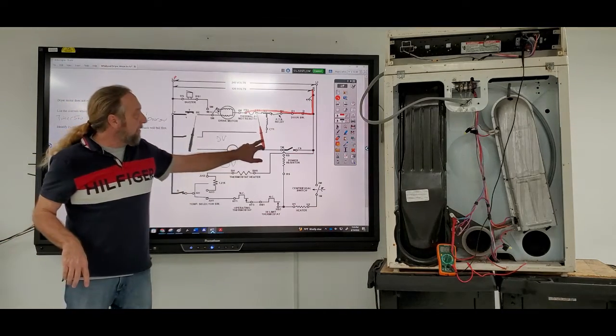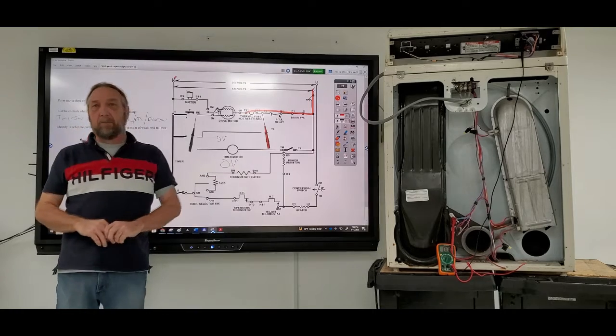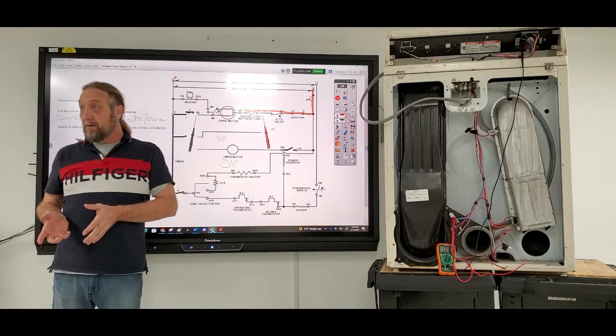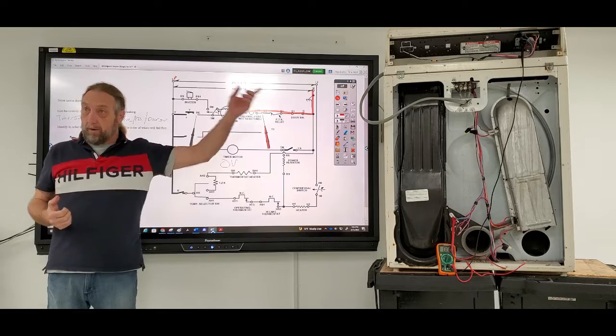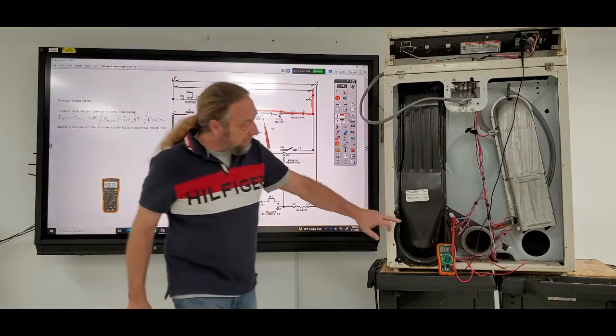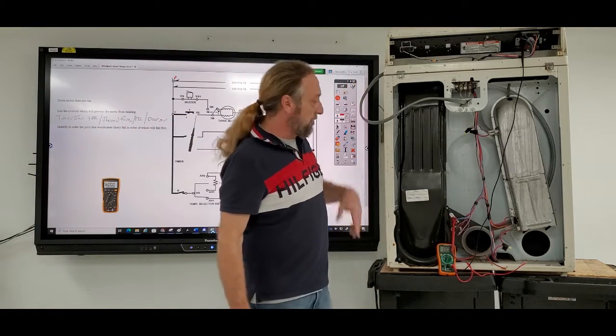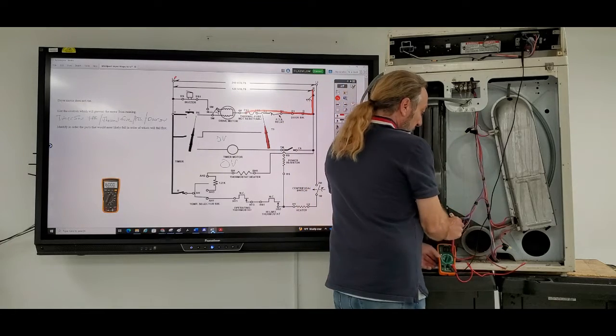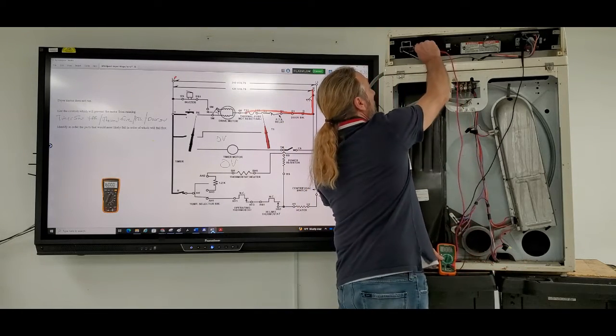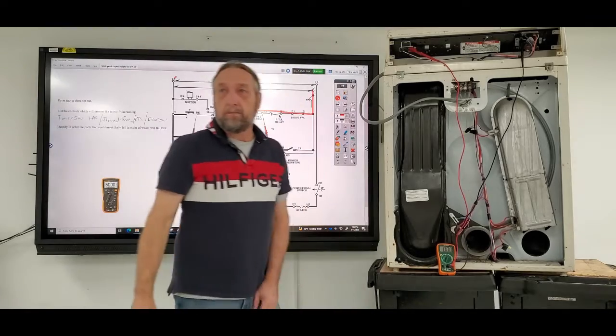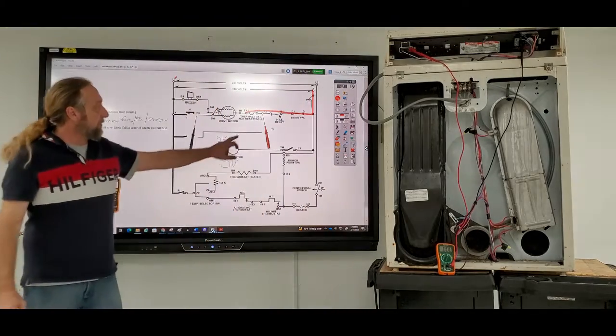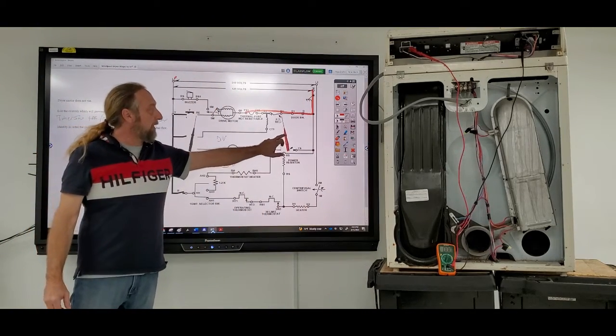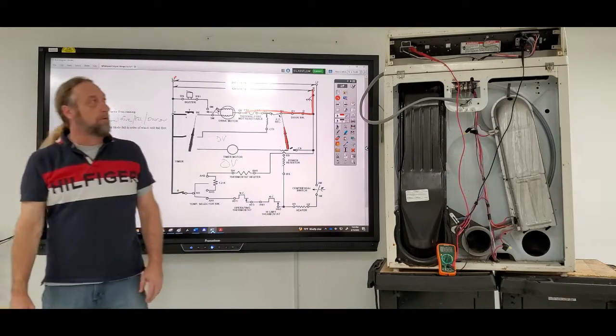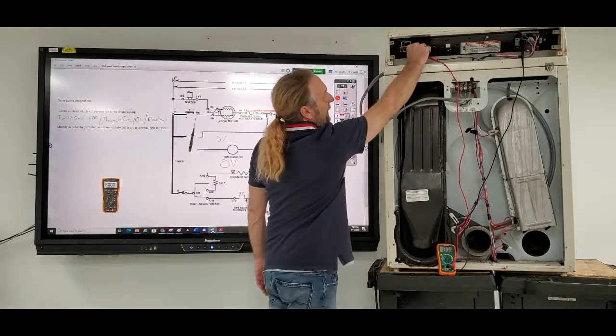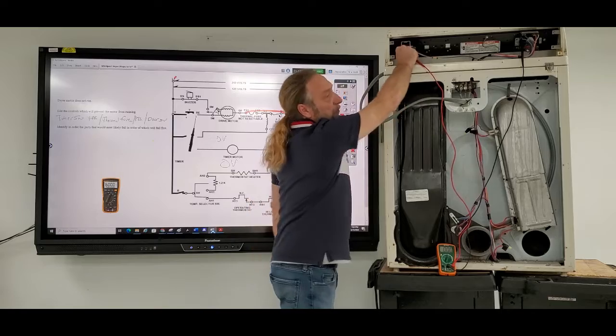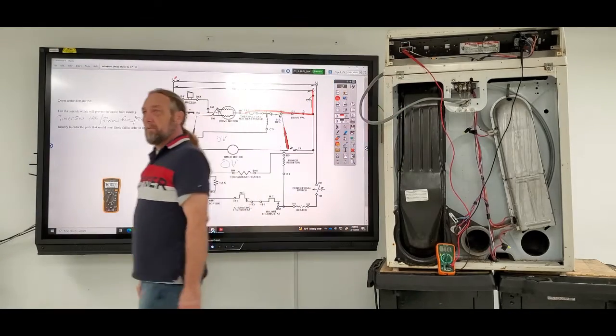Now I went here, and I'm on the relay, the start switch, where it goes to the fuse. So this other wire is going to go to my start switch. I'm going to take this meter lead to my start switch, and I still don't have voltage there. So I'm going to go to the other side of my start switch, and all of a sudden my meter says, hey, I got voltage. So now we know that the push to start has failed.